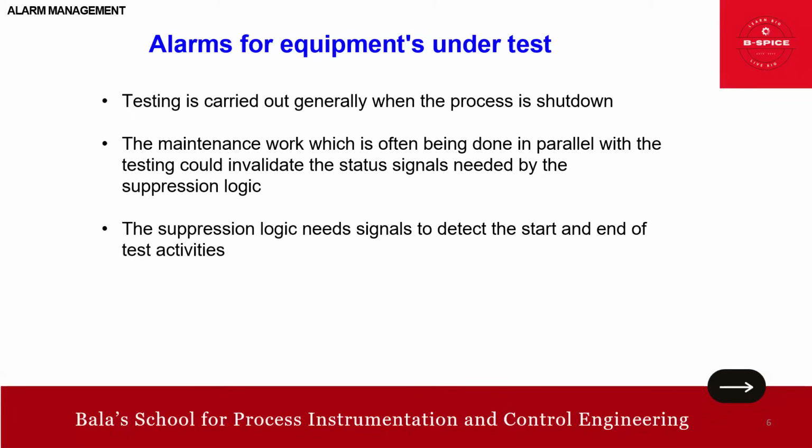The use of a timeout to ensure that the priorities are automatically reset should be considered. It is also important to recognize that equipment under maintenance is a common source of hazard, and care should be taken that alarms indicating these hazards remain active. So this is one way of doing shelving, for alarms for equipment under test. That's all I have for the shelving concepts.